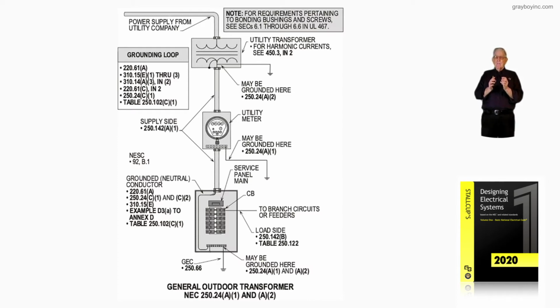And as an example, it's the major portion rule, which is 50%. Now you can find this 50% in 400.5(A) as an example in the NEC. But as an example, and most all inspectors go along with this concept: if you had 100 amps on L1 neutral load, L2 100 amps, and L3 100 amps, all neutral load, and 51 amps or more of that load was harmonic nonlinear loads, then the neutral would be considered current carrying in the electrical system under certain conditions. See?